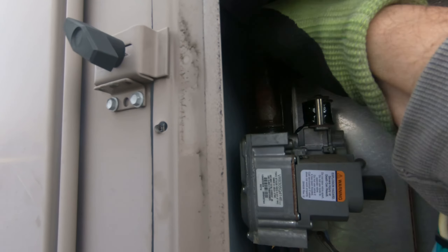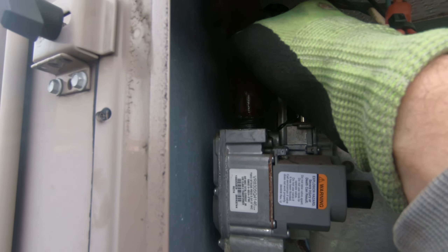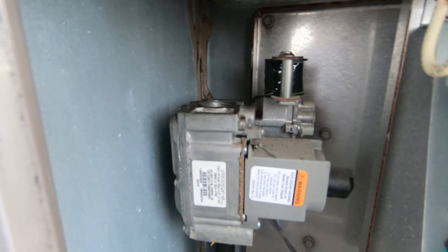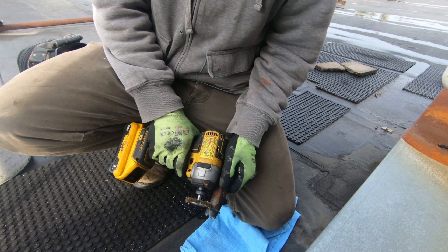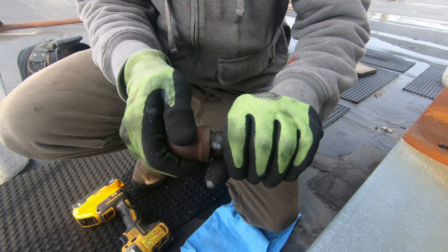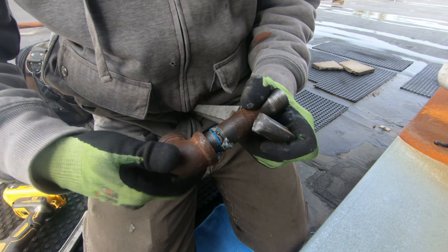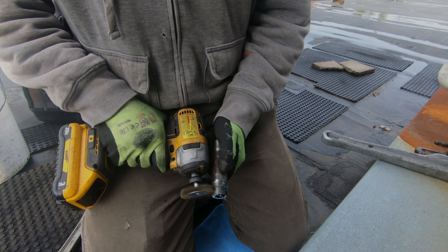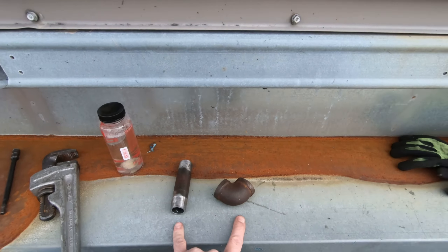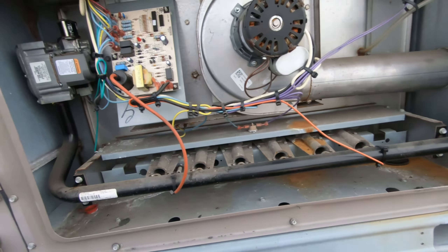I'm going to have to give these other units another look too, to make sure everything over there is good and tight. I managed to get that out with my hand — no wonder it smelled up the gas here. Let me clean all these threads up and we'll get everything tightened back down. I'm going to take this apart too and redo everything — it seems tight but I don't trust anything now. My fittings are all cleaned up, I'm going to wipe down that valve and I think we're going to be good to go.